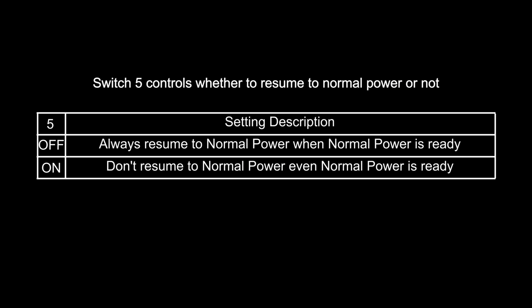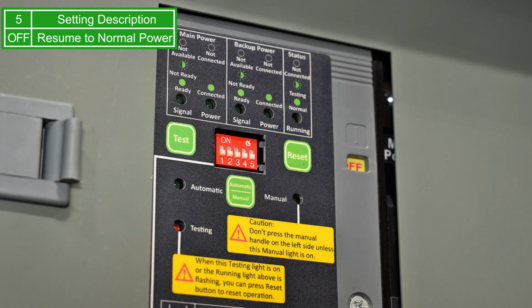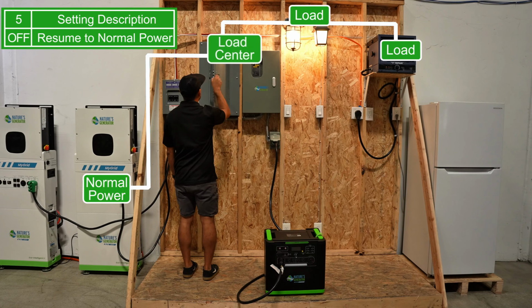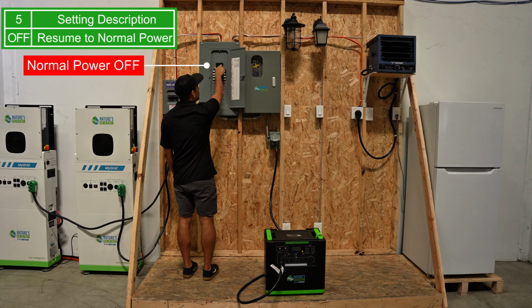Lastly, let's look at the fifth switch. Off means returning to the normal power when it is ready. On means to stay at backup power even when the normal power is ready.